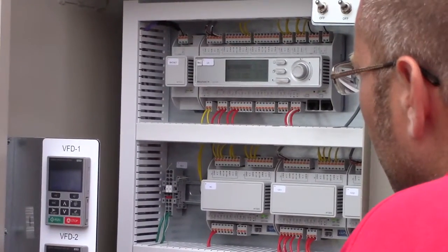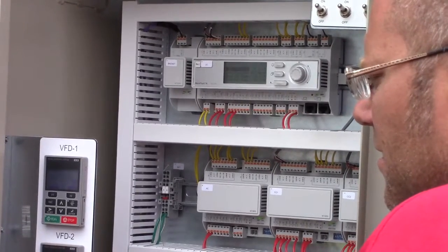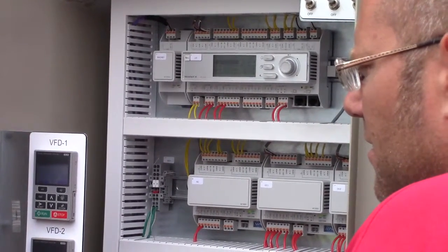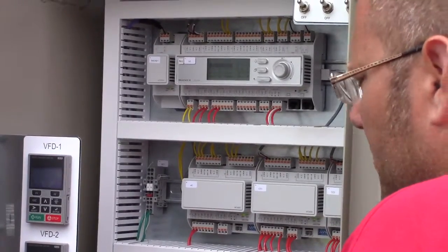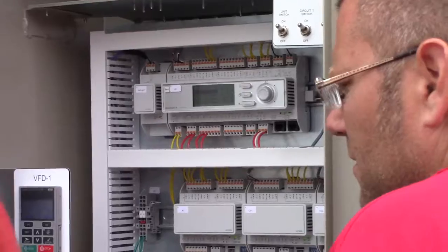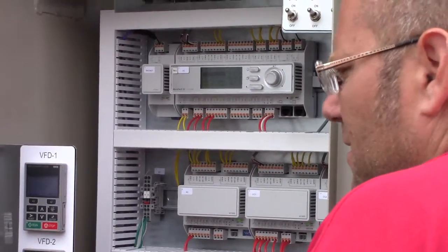In this case, it'll start off in a pressure mode and just try to maintain pressure until it gets going. Goes into a superheat control. It might start off at like 15 degrees and then work its way down. So you may see it anywhere from 5 to 15 or something like that. Just depends on it. So they give you what the target is as well as what you're actually doing, so you can see the difference.